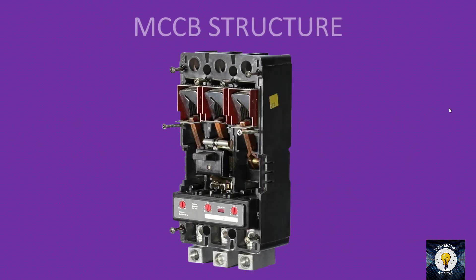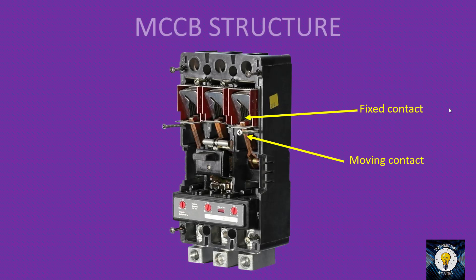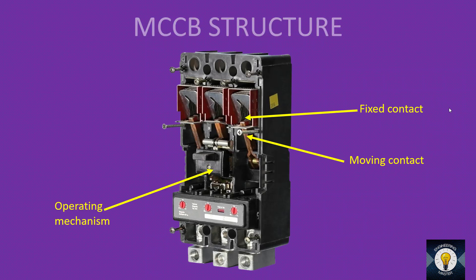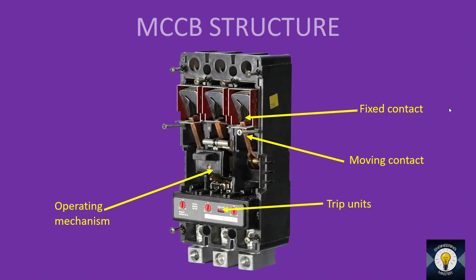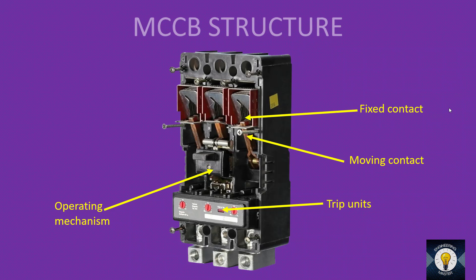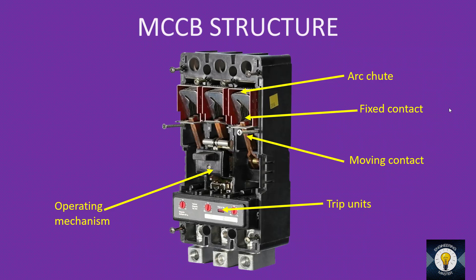If we look at an MCCB structure, we can see the fixed contact and the moving contact. Through the fixed and moving contacts, electricity flows. While tripping, the moving contact will fall apart and interrupt the electricity. Next is the operating mechanism — an on/off knob switch. Below this there is a trip unit, which consists of a bimetallic strip for overload tripping and a magnetic trip unit like a solenoid for short circuit tripping. Next is the arc chute, which is used to extinguish or quench the arc produced due to the sudden disconnection of the fixed and moving contacts.